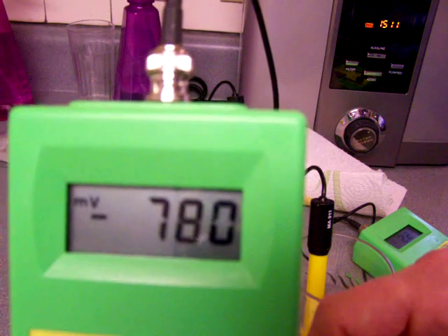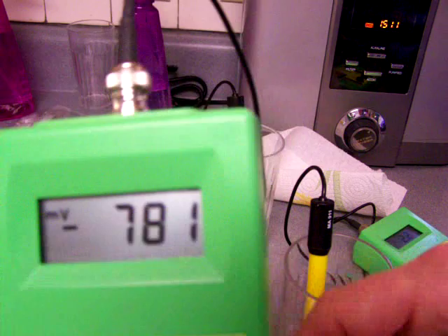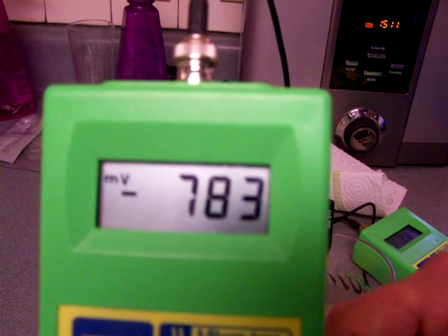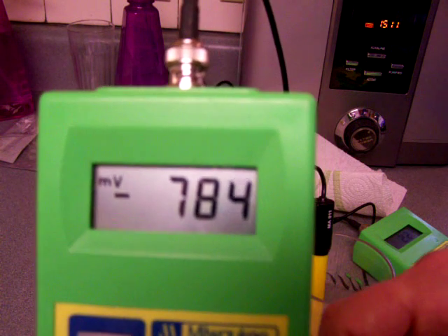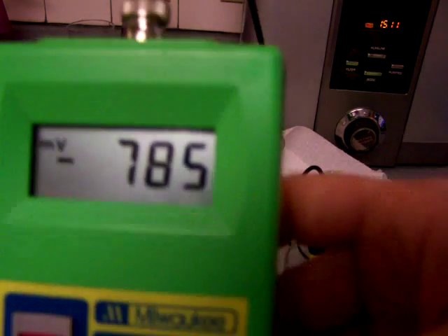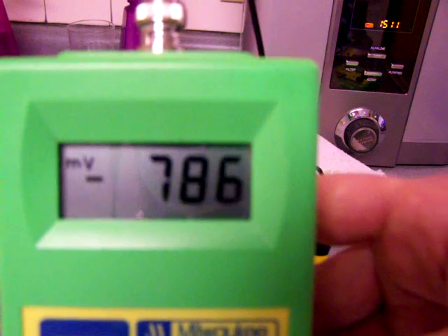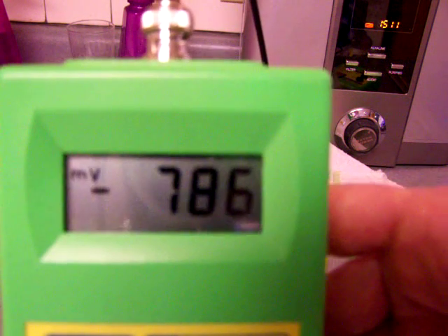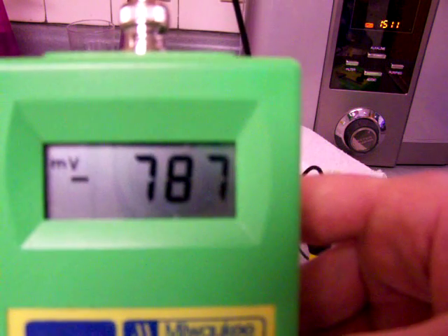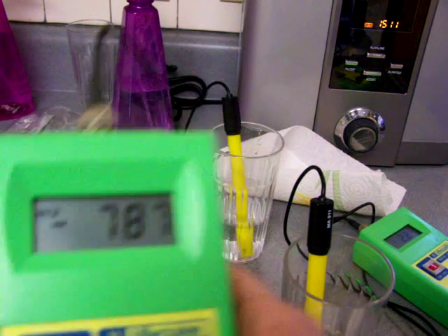Last night it was too clean to demonstrate how to clean, so I had to soak it in the ionized water overnight to dirty it up, to be able to show you what the results of cleaning the ORP meter are. This is very simple, took about a minute.